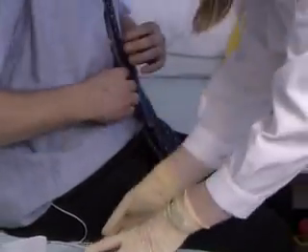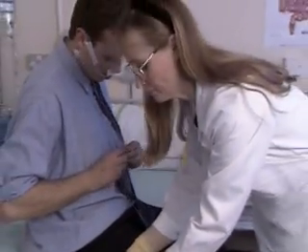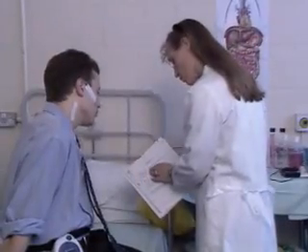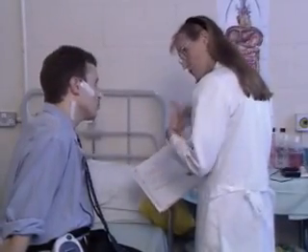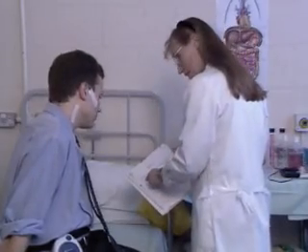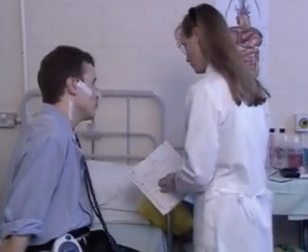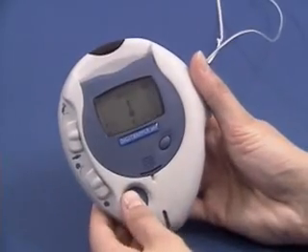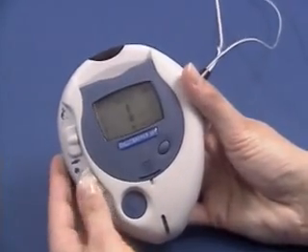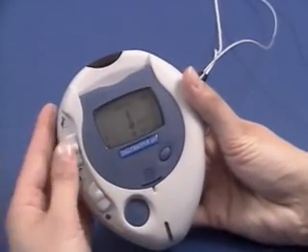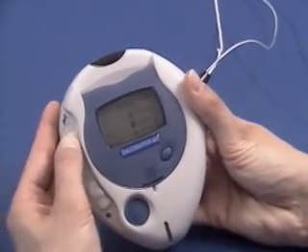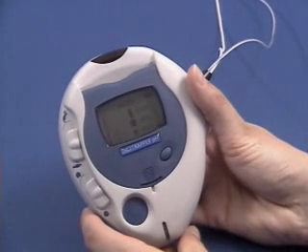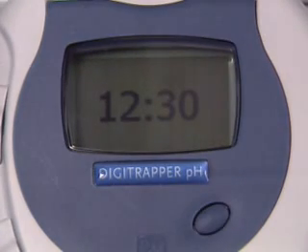The catheters are generally hidden beneath the patient's clothing so that they are out of the way. We want you to try and eat and drink as normally as you can during the test. Before starting the recording, diary record keeping is explained, both the electronic and the written diary. Electronic diary events are entered using Digitrapper's period and event keys. Further information about symptoms and meal times are recorded in the written diary using times read off the Digitrapper internal clock. To activate the clock, press the small blue button immediately below the screen.